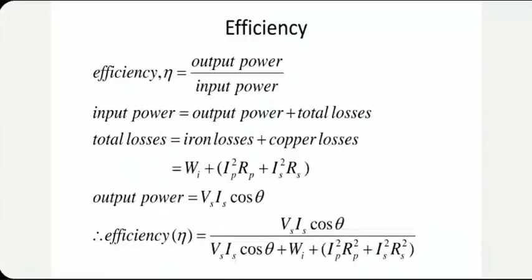One thing to remember: if the load is changing on the secondary side, current will change. That does not affect the iron losses very much, since iron losses are more or less constant with the load current. But copper losses change significantly. This factor has to be kept in mind when making efficiency calculations.